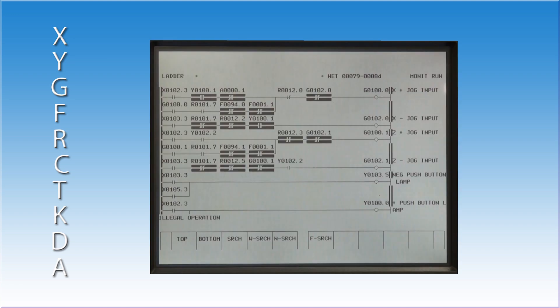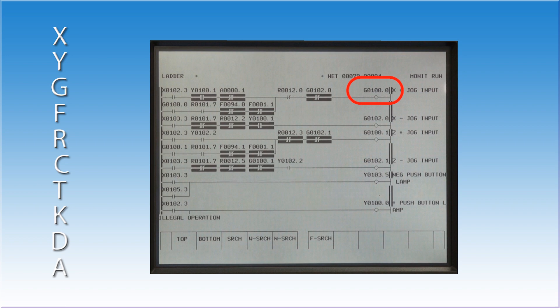Pushing that button activates an X address. The CNC, who is responsible for motion, only responds to G addresses. In this case, address G100.0 tells the CNC to jog the axis. Go into the ladder. Look up address G100.0. Look to see if it is going high. If it is not, the axis was never told to move. The CNC is doing what it thinks it's supposed to be doing, holding still.